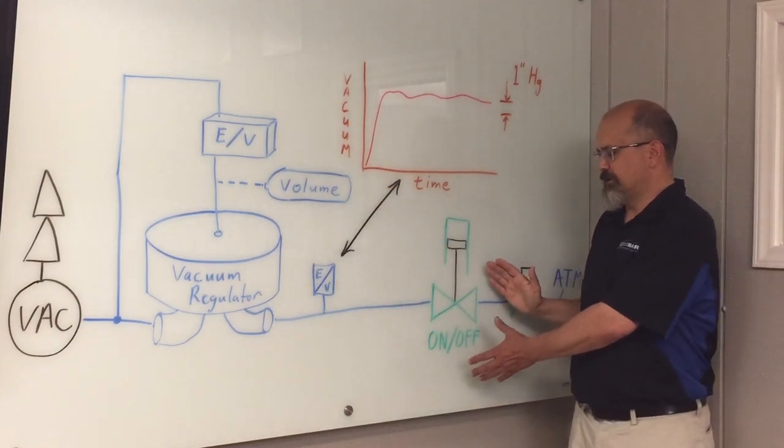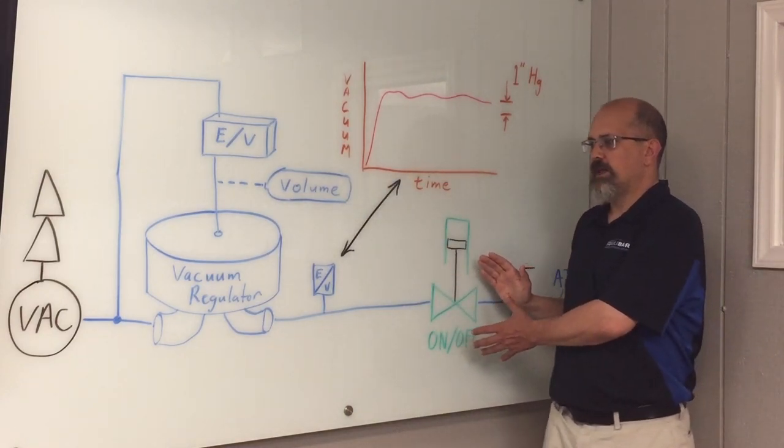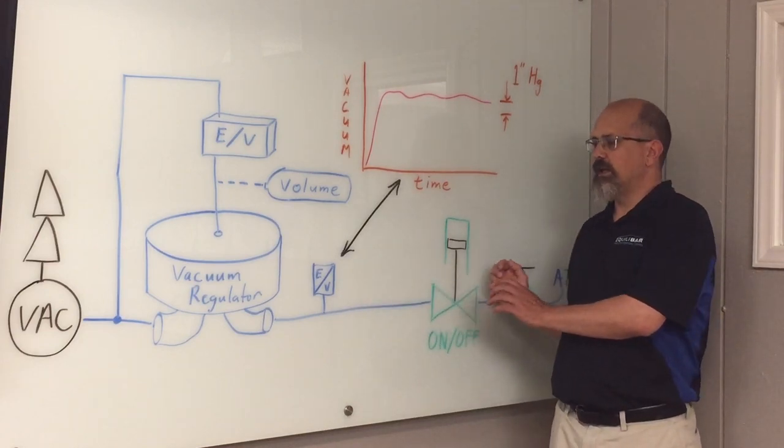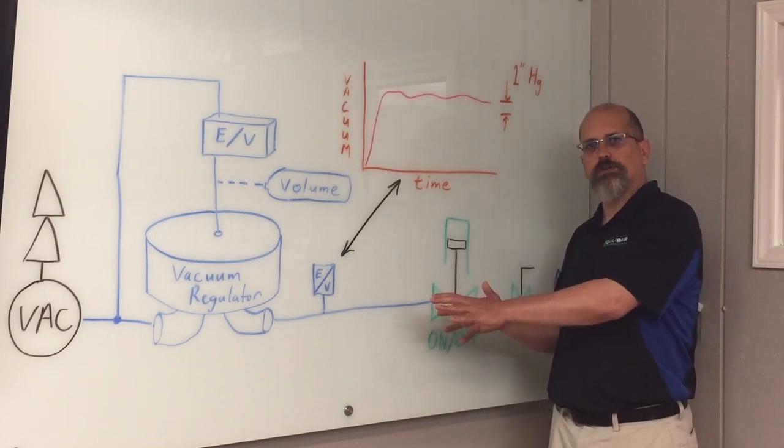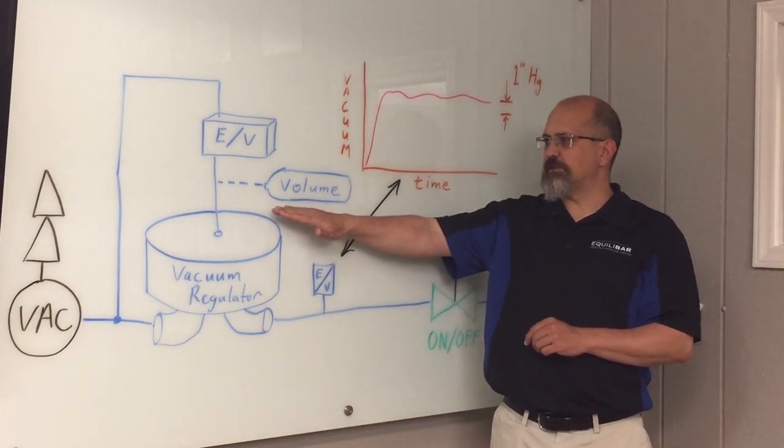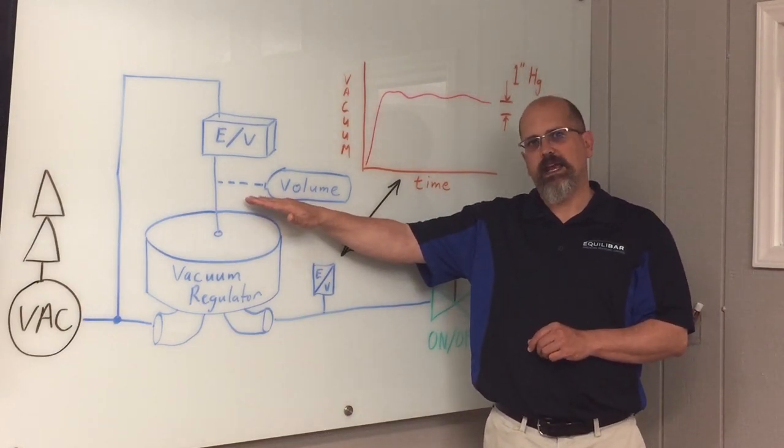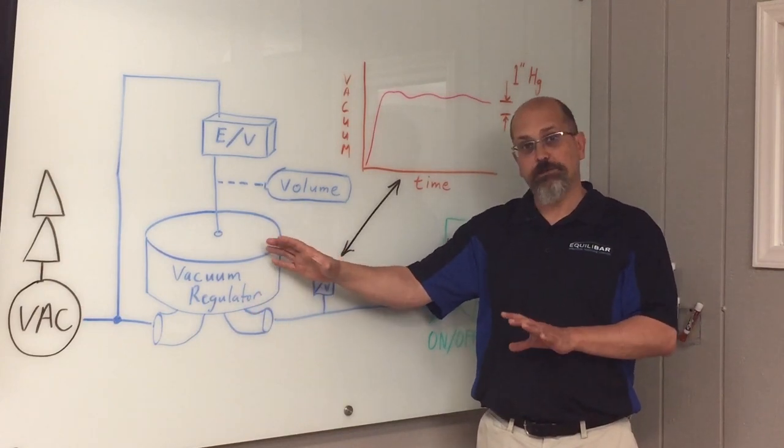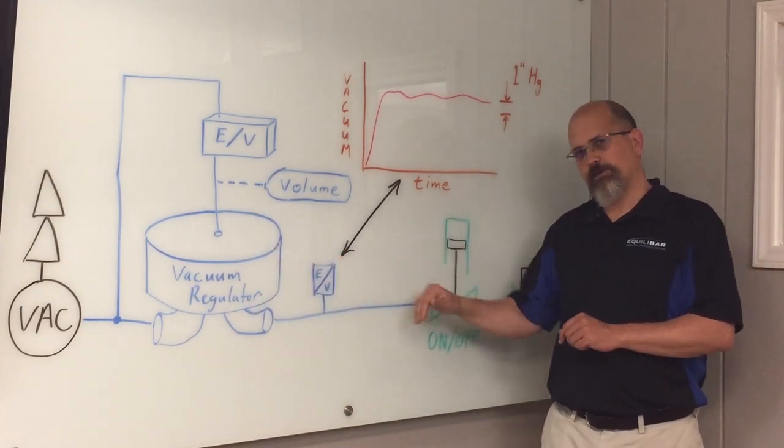And in a case like this where we have an on-off valve where the pressure that we want to control is stable, static, but the flow going in and out of the system alternates, we actually add some capacitance to the pilot, and that allows the vacuum regulator to quickly shift position and make up for that flow disturbance.